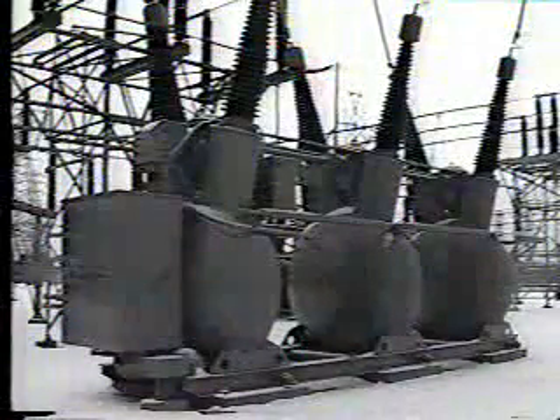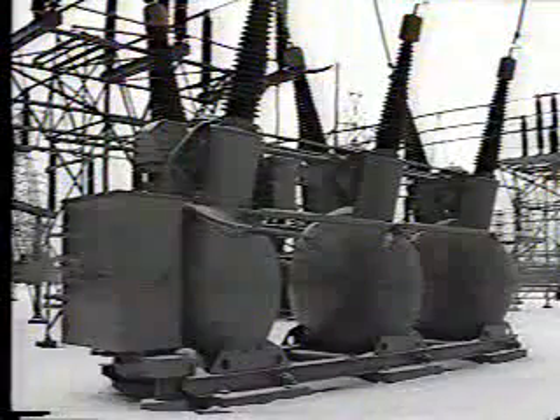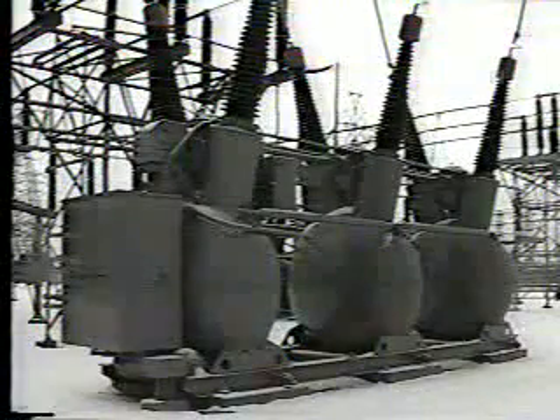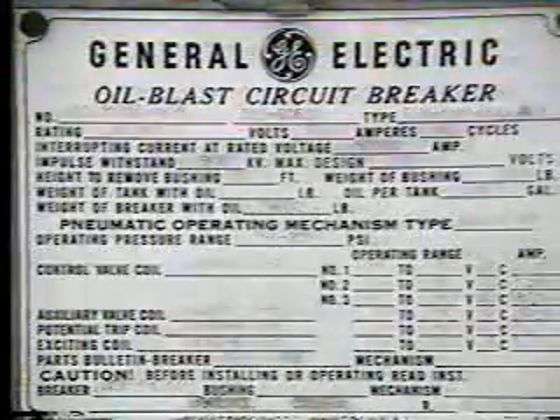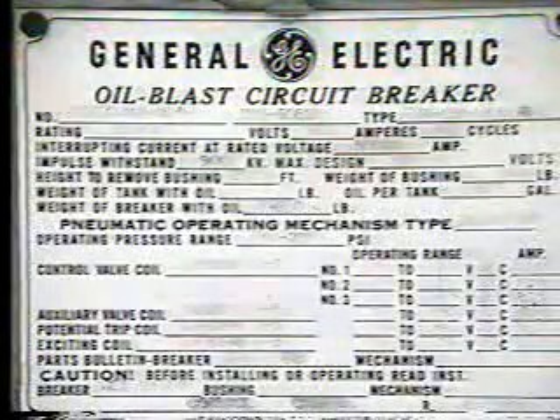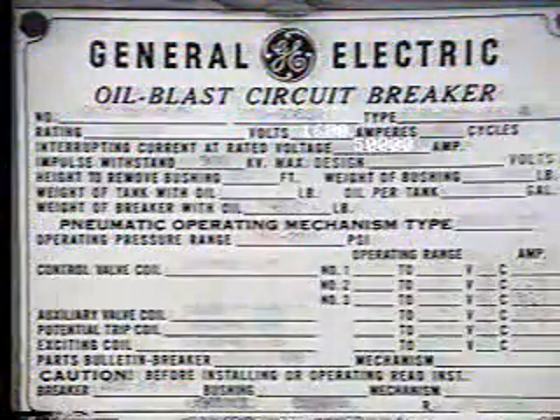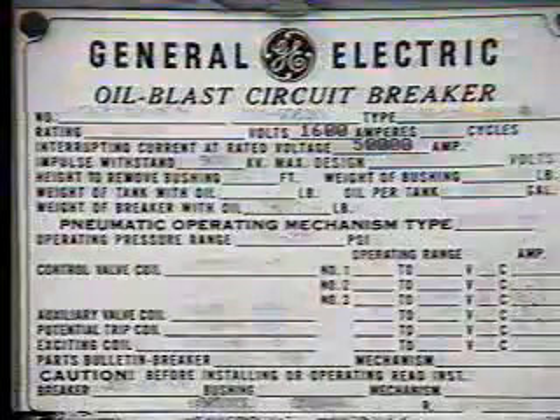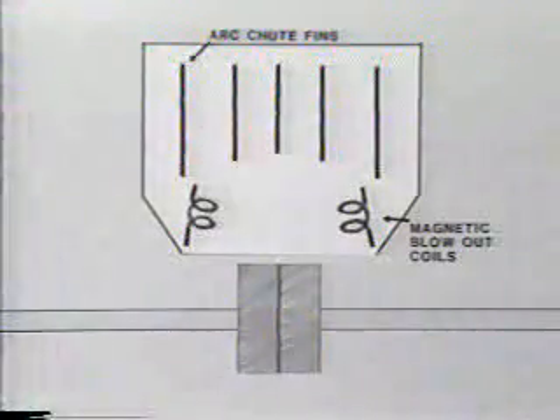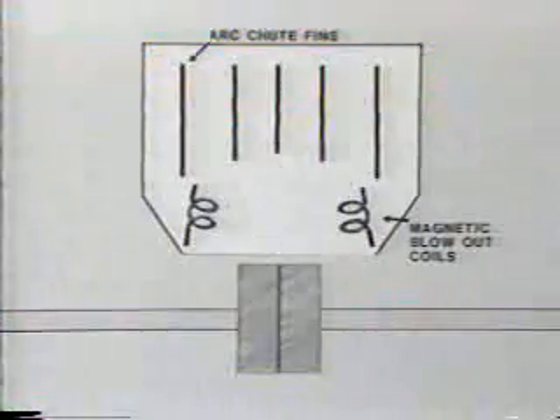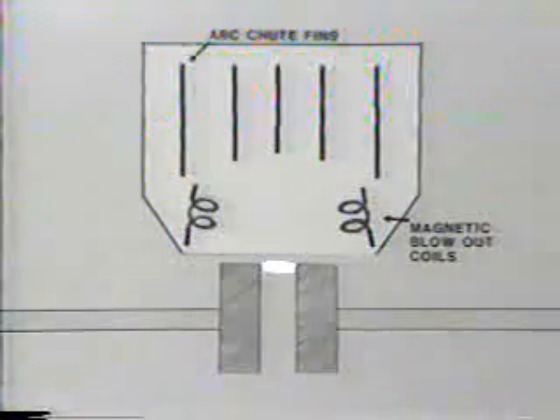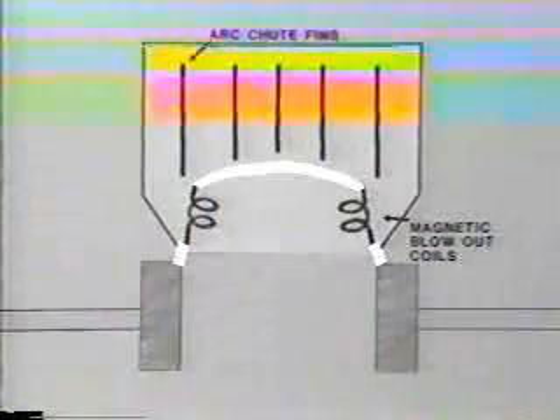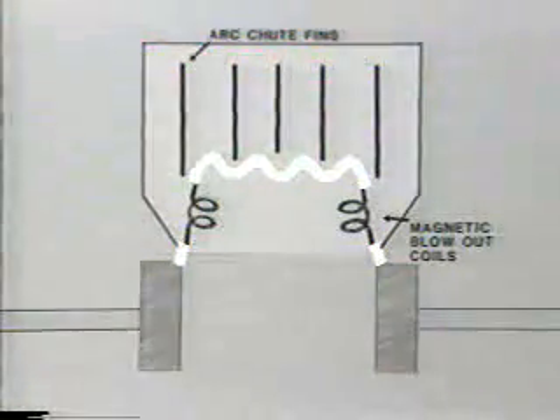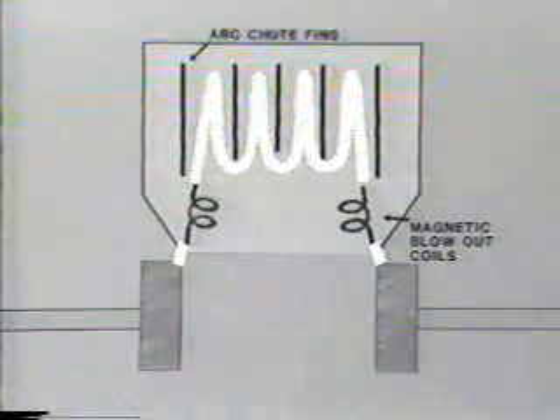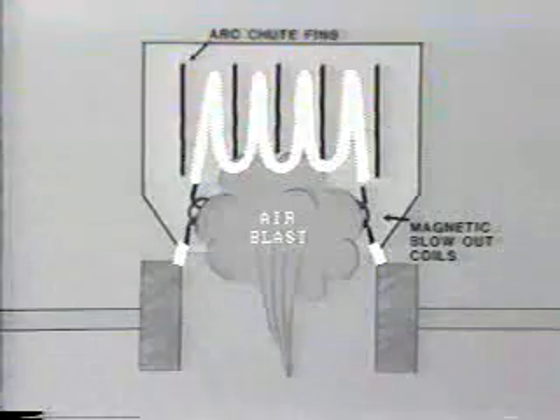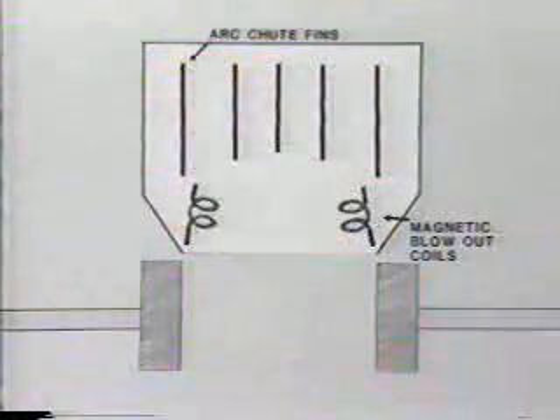Conversely, the circuit breaker would have little value other than as a manual switch if it were not coupled to protective relays. The circuit breaker is specifically designed to interrupt fault current, which may be 10 times or more than normal full load current. It achieves this by breaking the current flow in a specially designed interrupter. As the contacts open inside the interrupter, an arc is drawn. It is essential that this arc be extinguished immediately and the contacts thoroughly insulated from each other so as to prevent a restrike, which could result in considerable damage to the breaker.